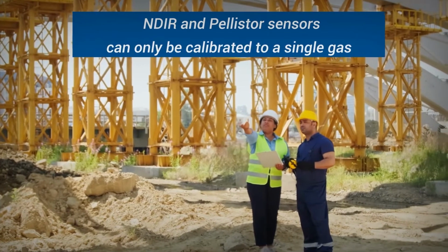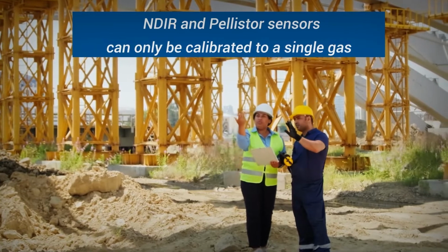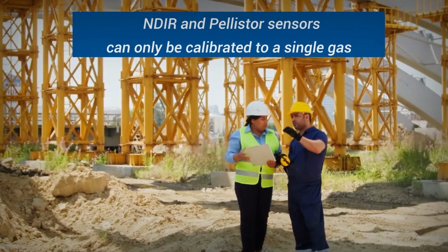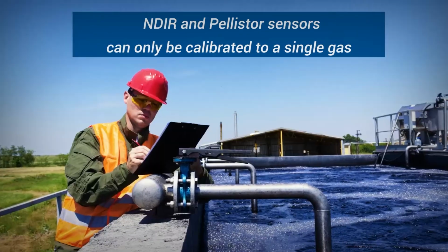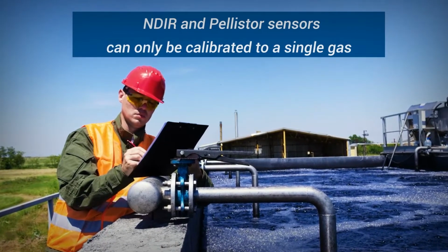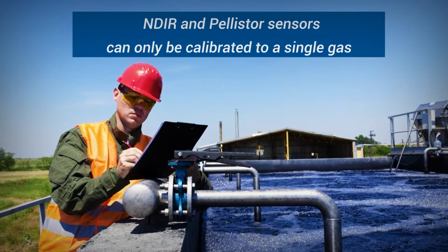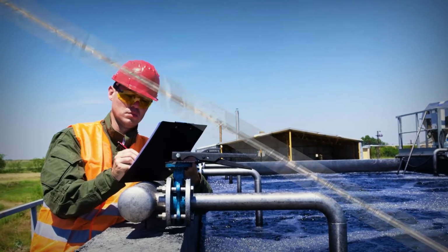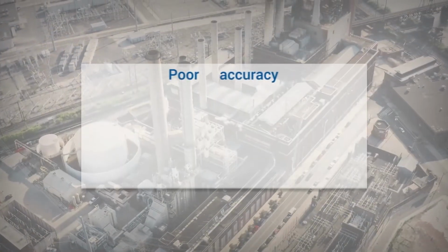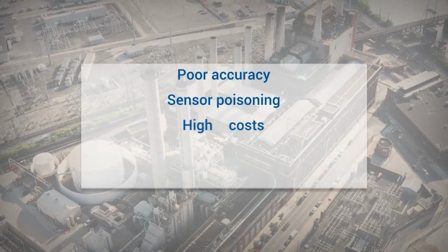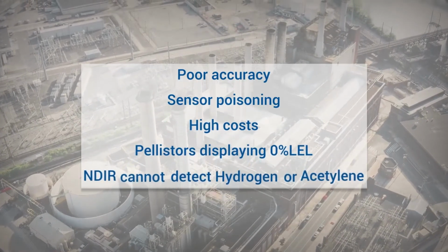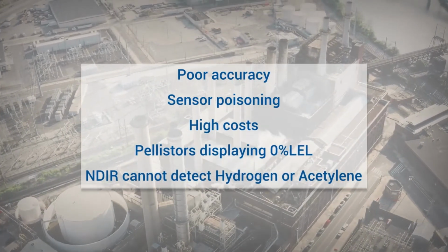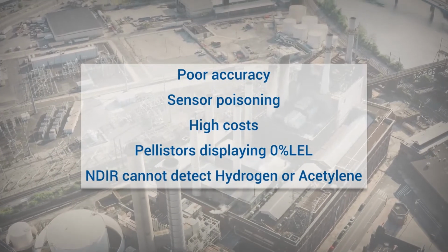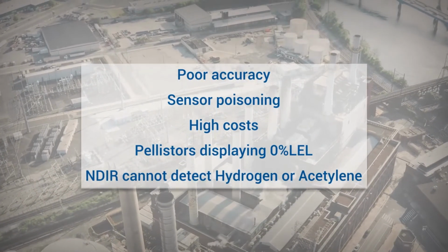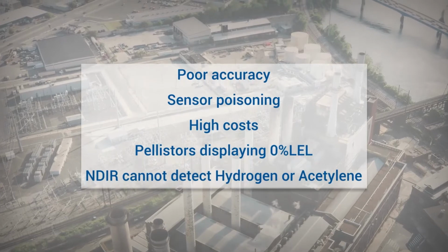NDIR and Pellistor sensors can only be calibrated to a single gas, inaccurately measuring or ignoring other combustible gases that are in the air, resulting in increased risk and costs via false alarms. Further risks include poor accuracy, sensor poisoning, frequent calibration, and replacement cost. Pellistors potentially failing and still displaying 0% LEL, and NDIR cannot detect hydrogen or acetylene.